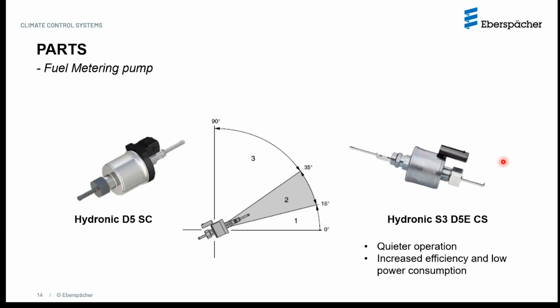The pump itself, both on the first generation and the third generation, is a pulse pump. So the ECU will send 12-volt pulses to the pump. And based on the pulses, the piston in the pump is basically pulled back and released. And so that moving action of the piston back and forth is what allows for fuel to be drawn into the pump and pushed towards the heater. The ECU regulates the flow of fuel just by increasing or decreasing the frequency of the pump.